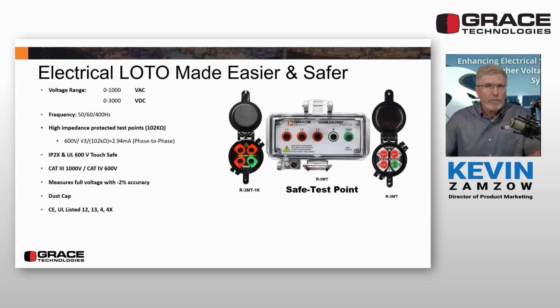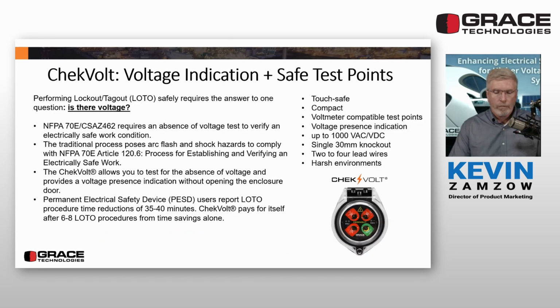Our current line of high impedance safe test points support through panel testing for the absence of voltage up to 1000 volts AC or volts DC. They are approved with transients up to 8000 volts, which makes them suitable for Cat 3 1000 volt AC and Cat 4 600 volt AC uses. In 2023, we started offering a permanent electrical safety device that combines voltage indication and safe test points in a single 30mm knockout. It was initially released to support up to 1000 volts AC and 1000 volts DC.